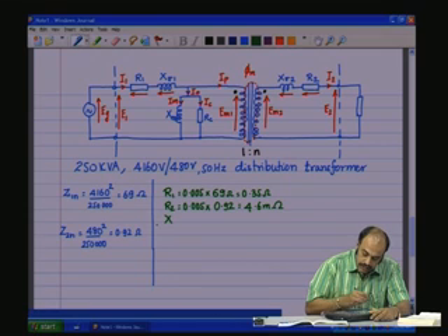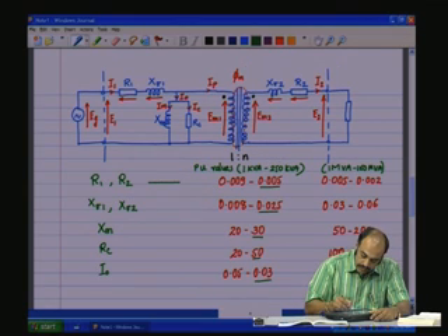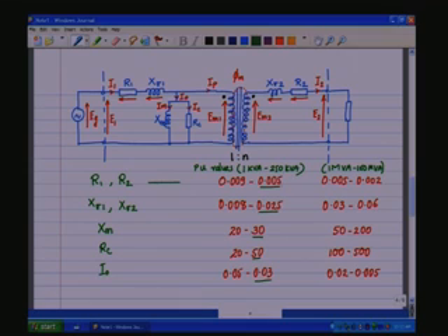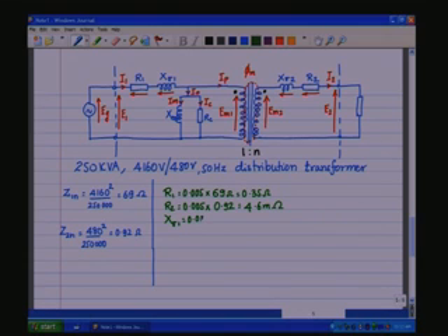Now, the leakage reactance X sigma 1. The per unit value is 0.025 for a 250 kVA transformer, so 0.025 into the base impedance for the primary side, which is 69, will give you 1.7 ohms. And X sigma 2, the secondary side leakage reactance, is 0.025 into the base impedance on the secondary side, which gives you 23 milli ohms.